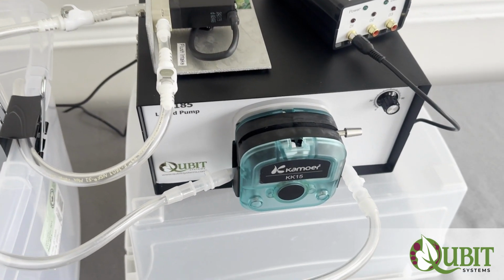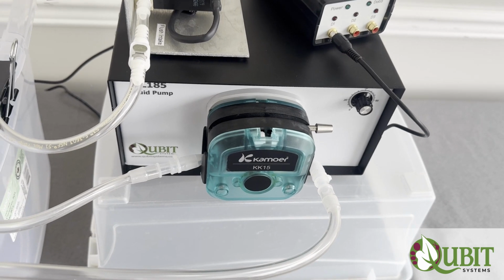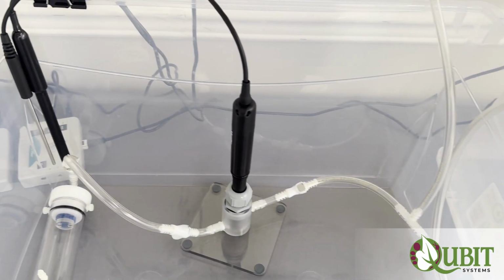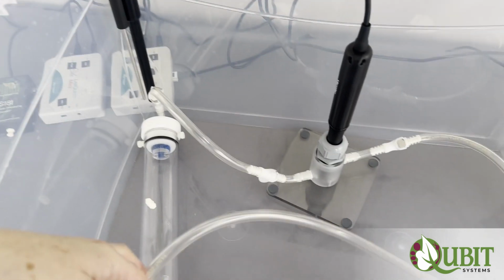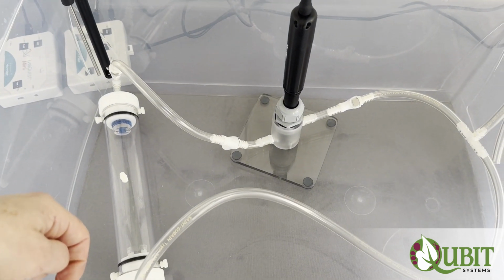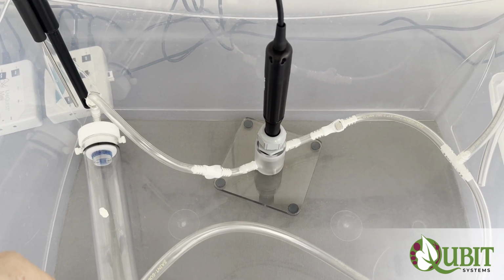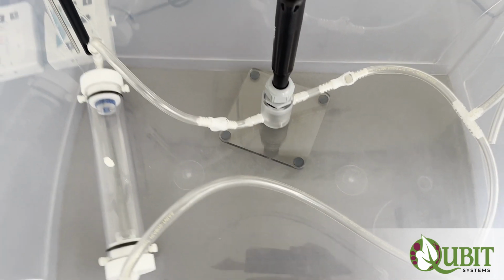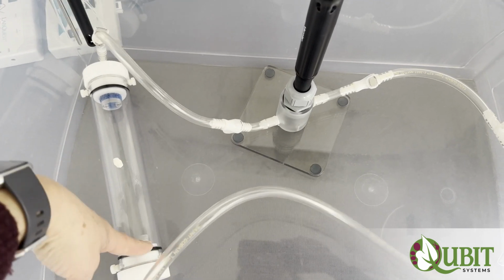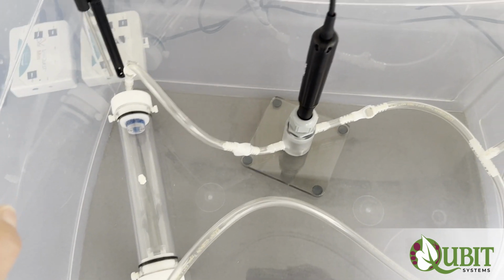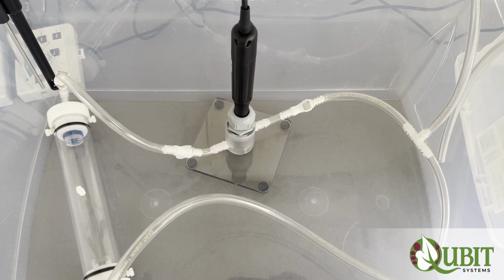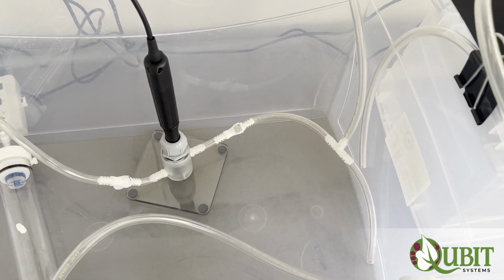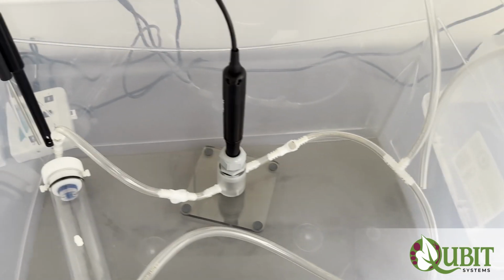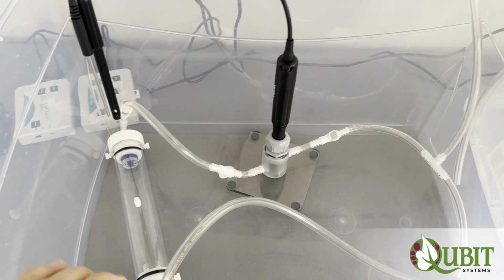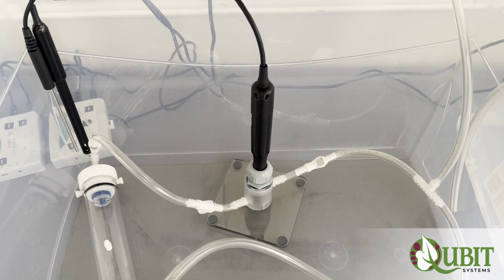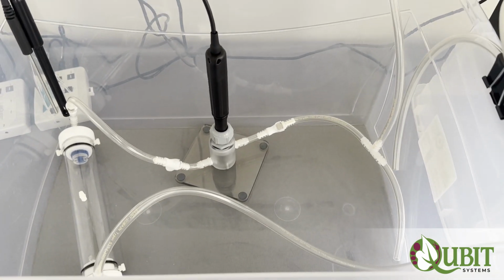The flow range of this pump is from about 130 mils to about 600 mils, and depending on whether the small chamber is used or the larger chamber is used, that flow rate has to be optimized. We provide suggestions in the manual for the flow rate, but it will depend, of course, on the size of this chamber, because we can provide custom lengths of these respirometer chambers, and therefore, you know, different volumes. So that's all there is with the setup of this system, and we will discuss other aspects of calibration in a separate video.